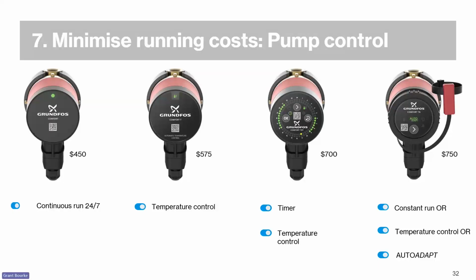So the one on the left, just a simple pump, runs 24 hours a day, but you can put an external timer on that and turn it off overnight. The next one's got an internal temperature sensor on it. As I explained in the previous slide, it will see the temperature rising in the ring main, and it'll turn off. It's got a cool algorithm in it that works out when to turn off and on again. The third one has got a little timer on it. It's a little clockwork timer, a bit like an old-fashioned timer, but it's a digital one. So your customer can really simply set the time of day, so it's got a temperature control and it's got a timer. So that'll really start getting your costs down. The last one here is auto adapt, which is sort of the top of the range for them.